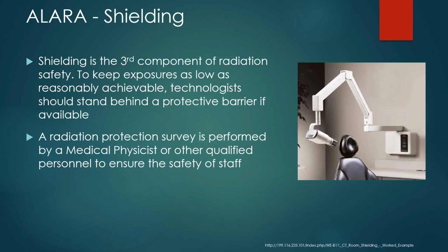Some dental facilities, due to their workload or the size of the room and the use of the surrounding areas, may not need additional shielding for the dental rooms. However, other units, such as cone beam dental CTs, may need additional shielding. Either way, a medical physicist should evaluate your X-ray installation.